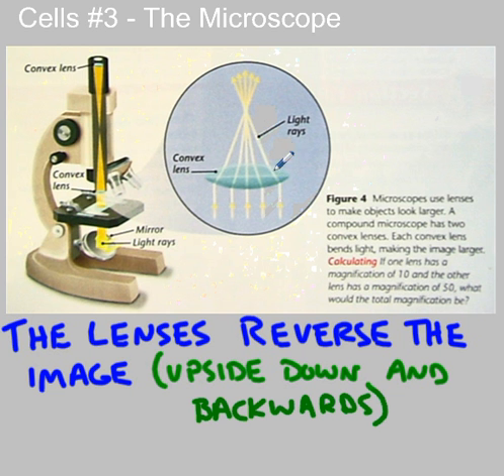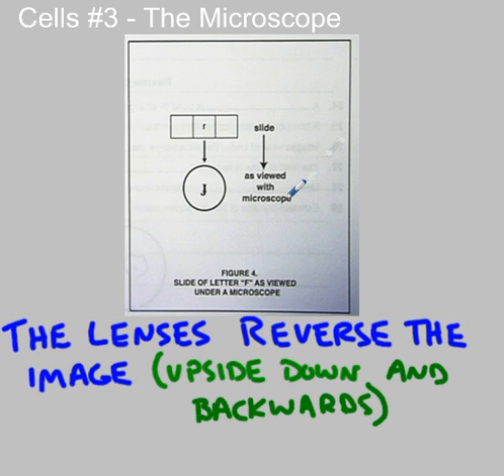It's also important to note that the way the lenses bend the light actually ends up reversing the image. The lenses reverse the image, so it's going to be both upside down and backward. When you try to center an image in the field of view, if you want the image to move to the left, you need to move the slide to the right. If you need the image to move down, you need to move the slide up — everything is reversed. Here, the letter F is placed on the slide right side up and normal, and you can see what the image looks like in the microscope: it is both upside down and backwards.